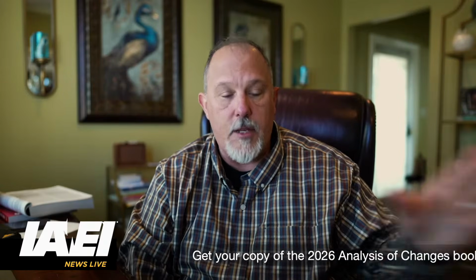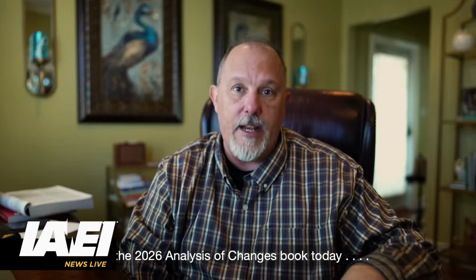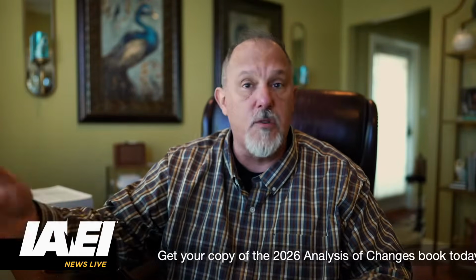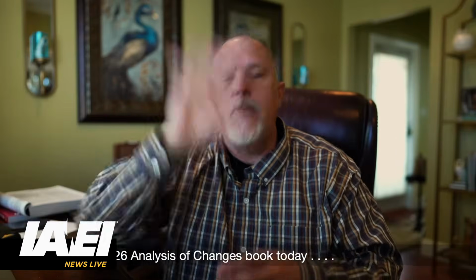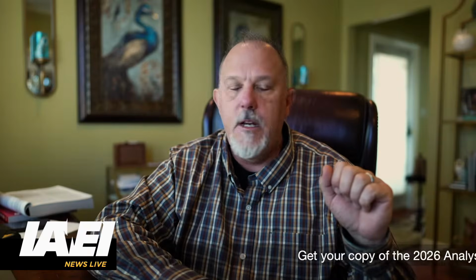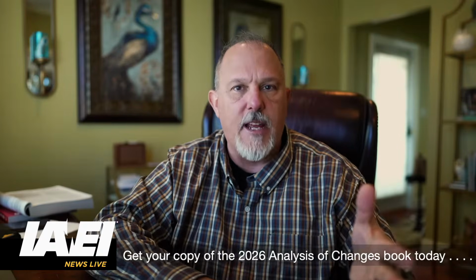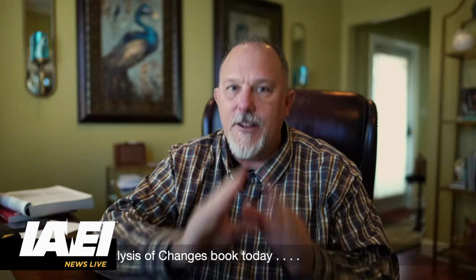I have heard individuals say, we always turn it off, so this would never apply because we never work on anything energized. All right? Well, you may say that, so let's take that at face value and say, okay, what about troubleshooting? And what do you troubleshoot? Motor control centers, industrial control panels. So then maybe they say, okay, I'm only talking about panel boards, switchboards, switchgear, transformers, things like that. Here's the issue with that.